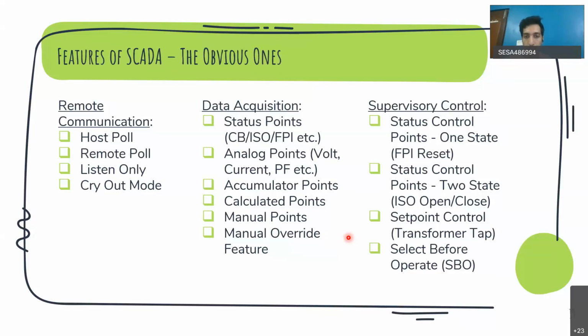Analog data can be acquired, like what is the voltage value, what is the current value, what is the real power, power factor, reactive power, etc. Those kind of things you can also read from field. Analog data means you are reading the current value. What is accumulator data? Accumulator is the data that is cumulative. Like for example, the total energy imported or total reactive energy imported, reactive energy exported through a particular period. Those kind of things which are cumulative, you can also measure them with the help of this data. Calculated points, we'll see in detail in the coming slides.